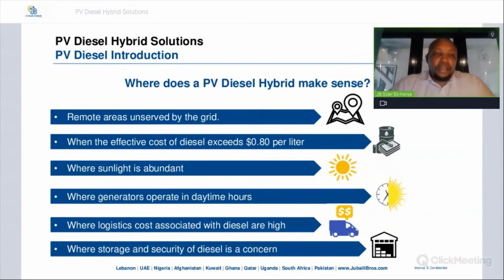So where and why does a PV diesel hybrid make sense? A PV diesel hybrid will be considered in remote areas that are unserved or underserved by the grid. These are areas where the grid has not reached or there's very intermittent power from the grid. We also want to consider a PV hybrid solution when the cost of diesel exceeds $0.80 per liter. And this is the case that we are seeing today. Due to the increase in global petroleum prices, we have seen a sharp increase in diesel fuel.